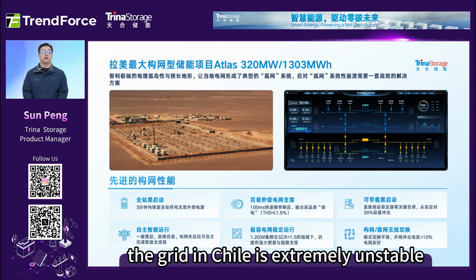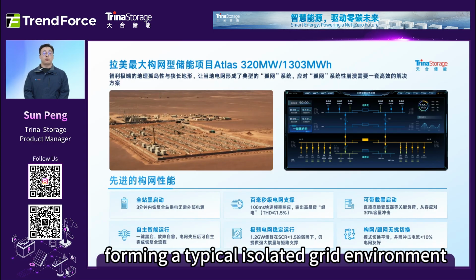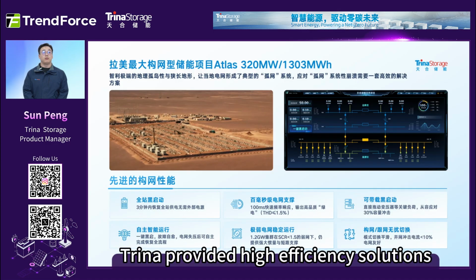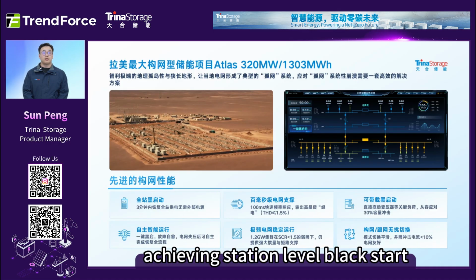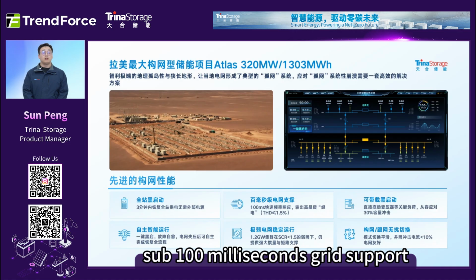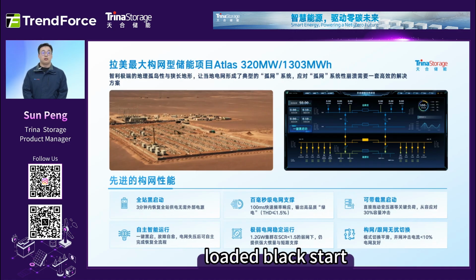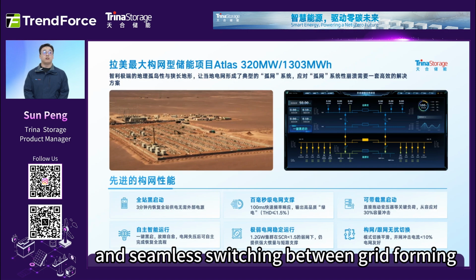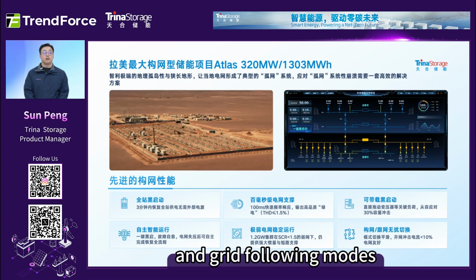The grid in Chile is extremely unstable, forming a typical isolated grid environment. Trina provided high-efficiency solutions, achieving station-level black start, sub-100 milliseconds grid support, loaded black start, and seamless switching between grid forming and grid following modes.